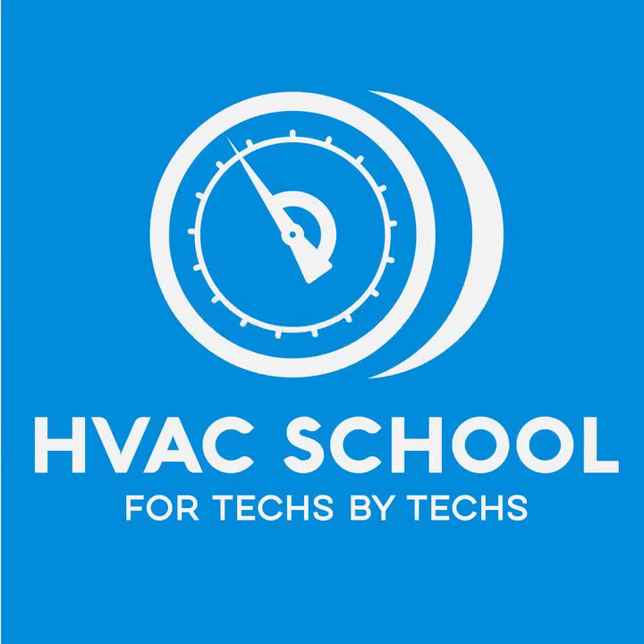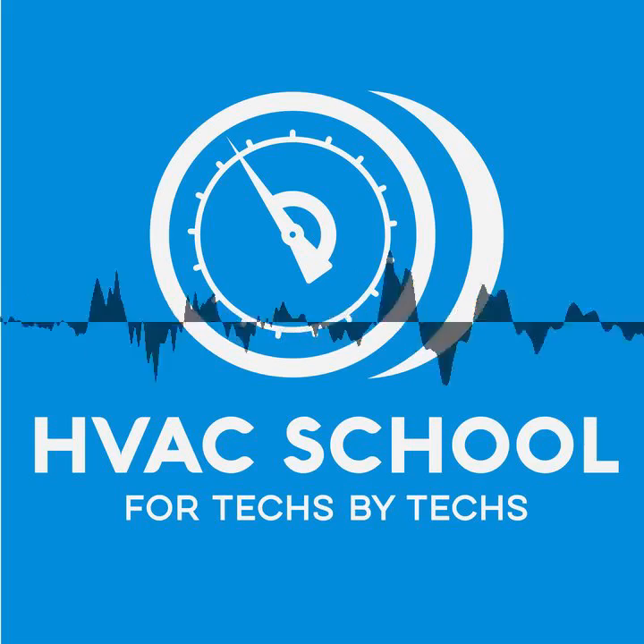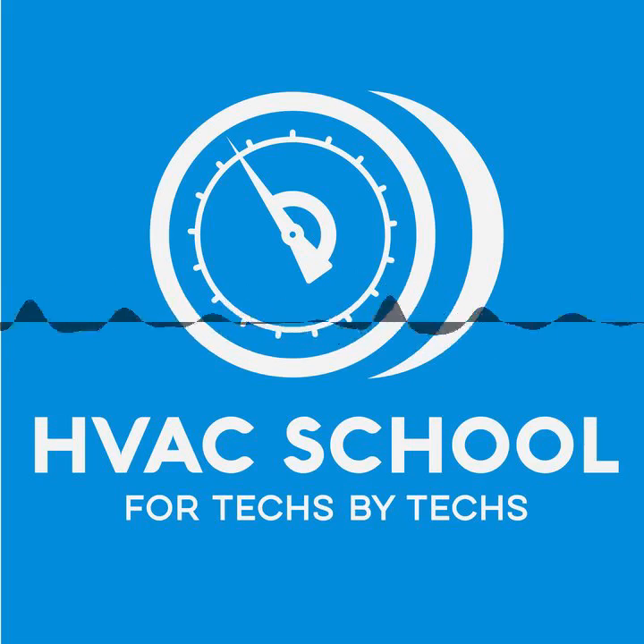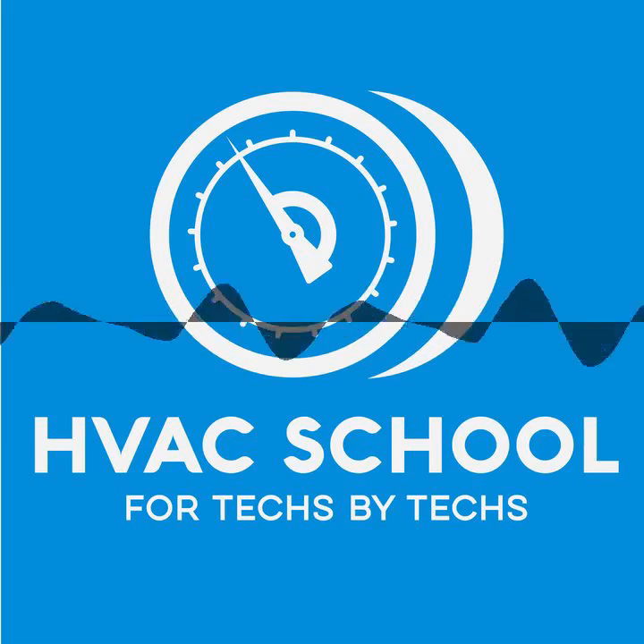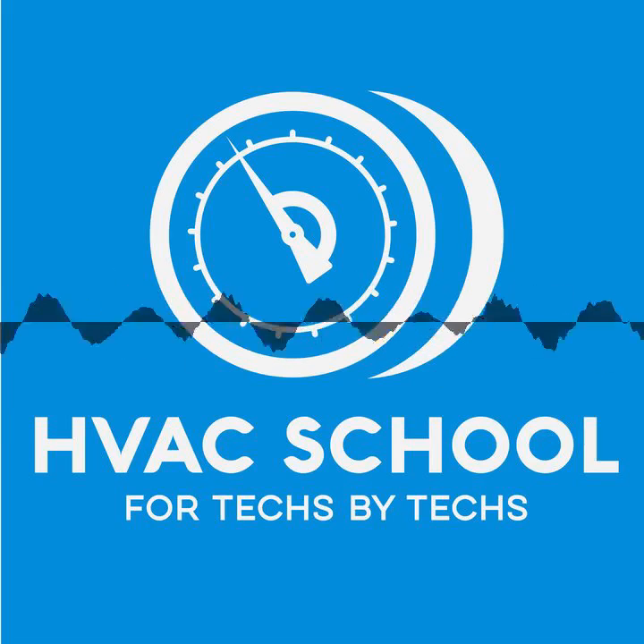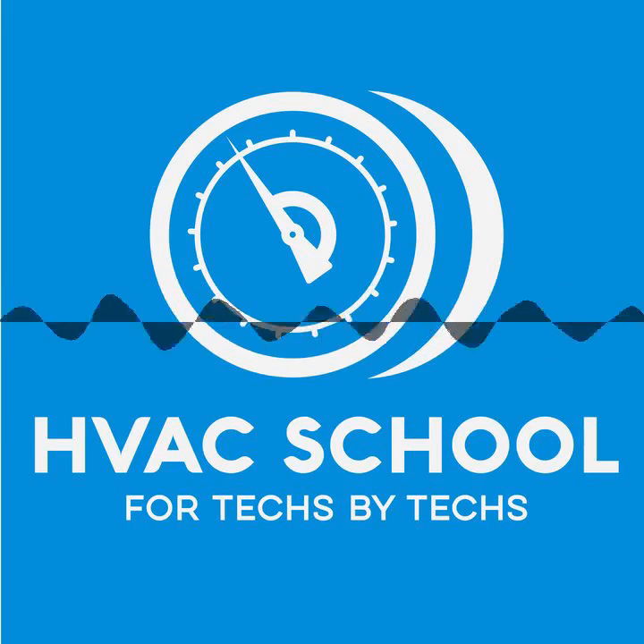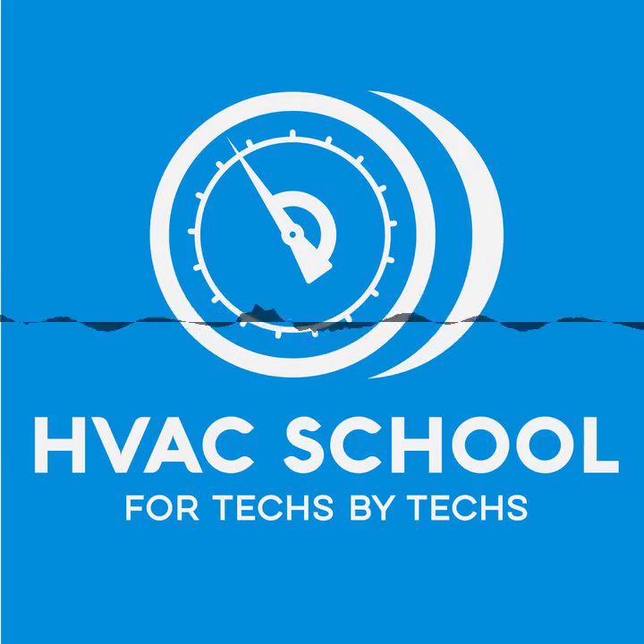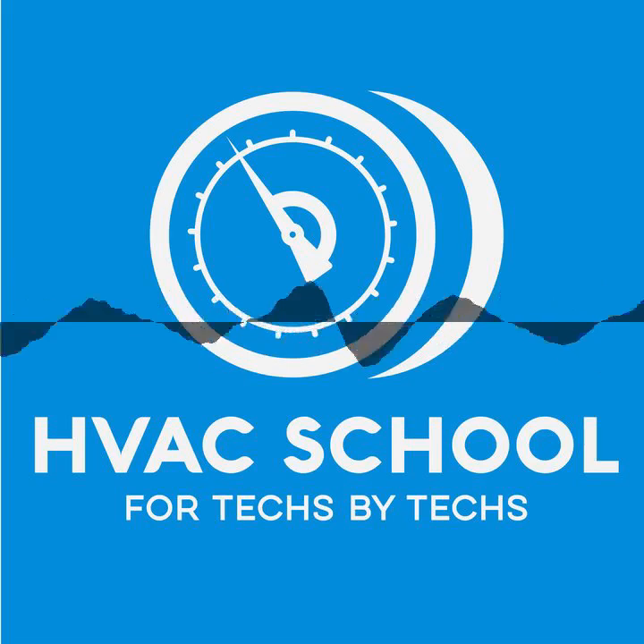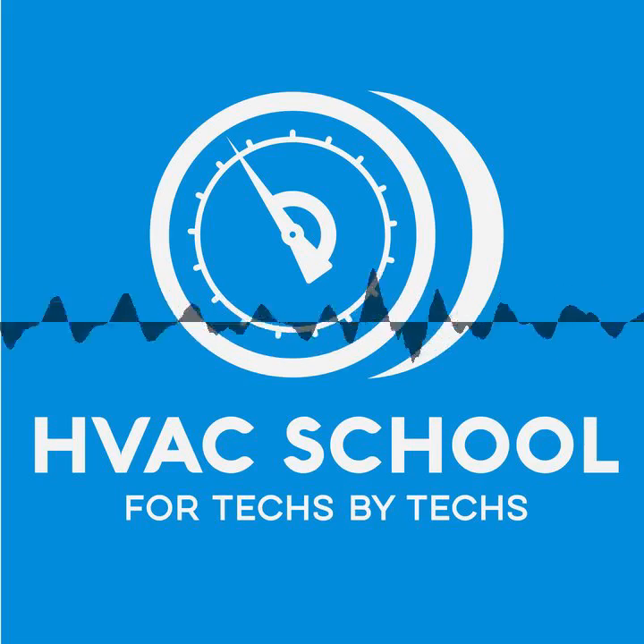So the TX valve is kind of like a balance beam, so to speak, on its side, where you have underneath pushing up the evaporator pressure and spring pressure. And I'll get back to that in a little bit. And on top, you have this pressure from the sensing bulb. So picture a line with the sensing bulb pressure on top and the evaporator and spring pressure underneath. Well, when that bulb pressure increases like that, it pushes down on the diaphragm, and the force it's pushing down with now becomes greater than what's underneath it, the evaporator and the spring pressure. This forces the valve open, and the valve now opens more, putting more refrigerant into the evaporator to match the new heat load. This results in somewhat of a drop in superheat and more refrigerant flowing into the evaporator now to take care of that extra heat. And of course, vice versa occurs.